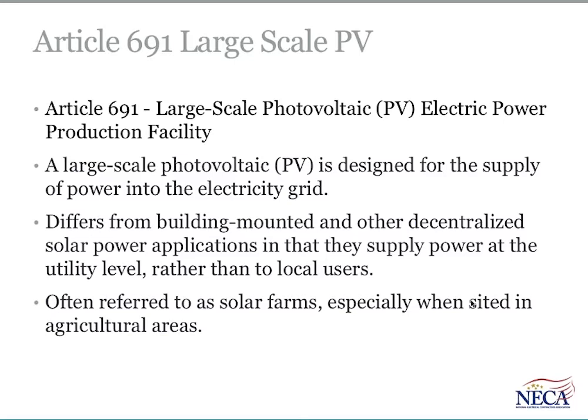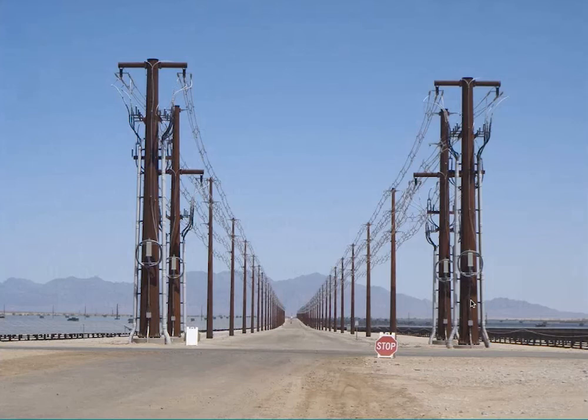The problem is there are a lot of large systems and a lot of design criteria used for these systems, and Article 690 really was incapable of providing the rules necessary for them. So that was the birth of Article 691, so that there are rules for these systems that are typically installed by private owners and actually owned by entities other than a serving utility. But certainly a utility system could be built to these rules as well. The photos I have are of a large-scale PV system. What you see looking down this road is all related to the PV system. This is at the 35 kV level. What you see on either side of the poles is the PV array, and that goes as far as the mountain.